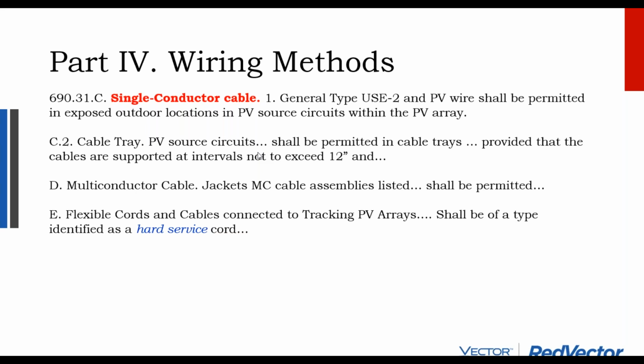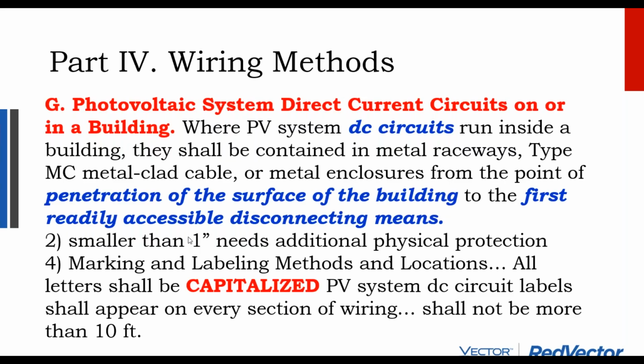Wiring methods. So we have a couple of different wiring methods that are allowed for solar. The main thing I want to bring up here is that you can use MC cable, and we're going to talk about that in just a minute. And also, you can use flexible cable, like welding cable, that has a lot more bend to it than your fine stranded cable. Can only be used in specific circumstances. So they're saying, okay, for solar tracking arrays, you have to have a hard service cord. Welder's cable, fine stranded flexible cable, really that can only be used inside battery banks.